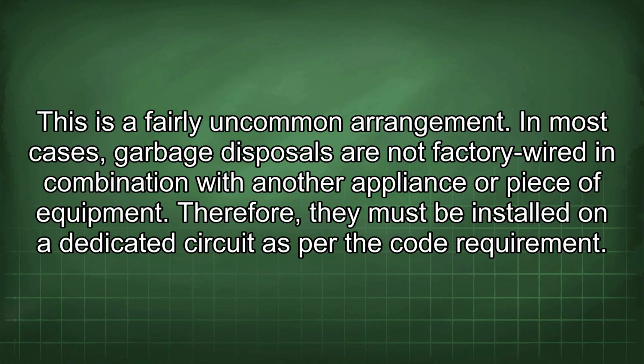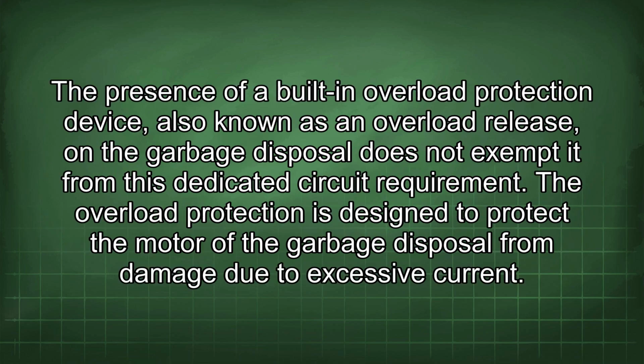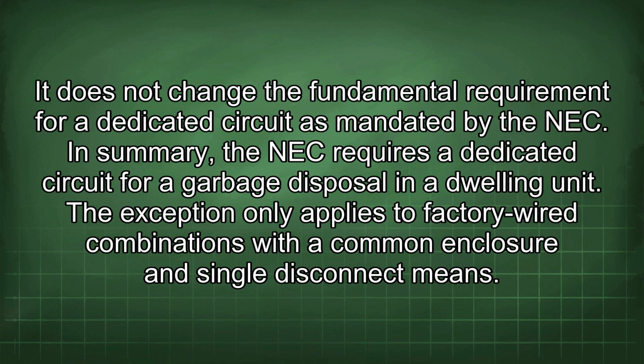This is a fairly uncommon arrangement. In most cases, garbage disposals are not factory wired in combination with another appliance or piece of equipment. Therefore, they must be installed on a dedicated circuit as per the code requirement. The presence of a built-in overload protection device, also known as an overload release, on the garbage disposal does not exempt it from this dedicated circuit requirement. The overload protection is designed to protect the motor of the garbage disposal from damage due to excessive current. It does not change the fundamental requirement for a dedicated circuit as mandated by the NEC.